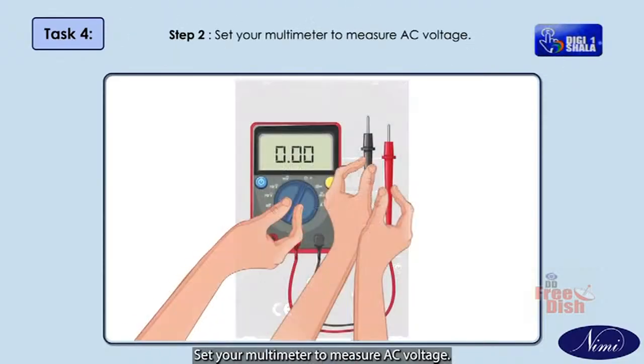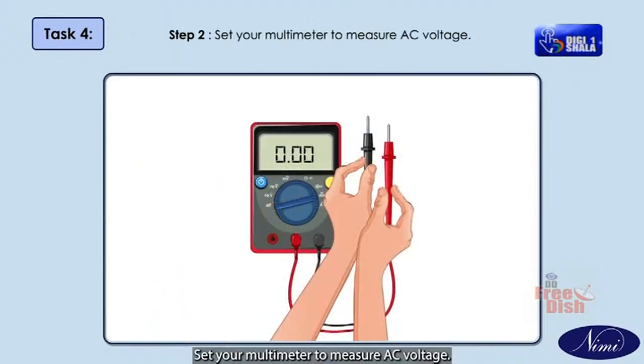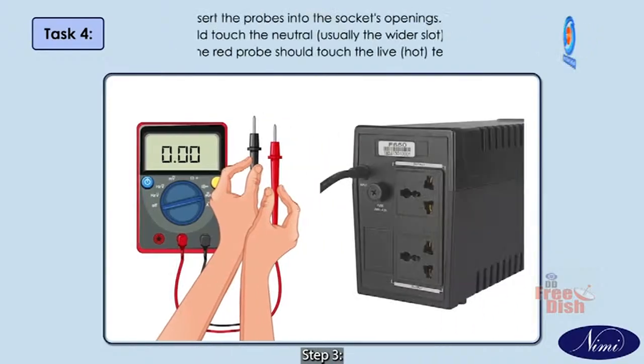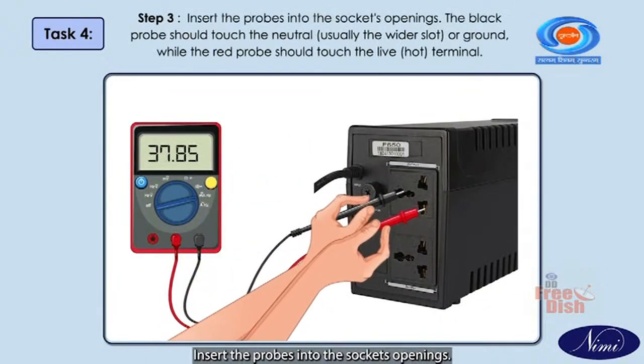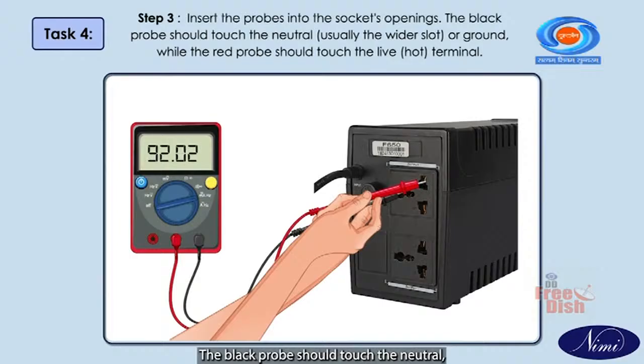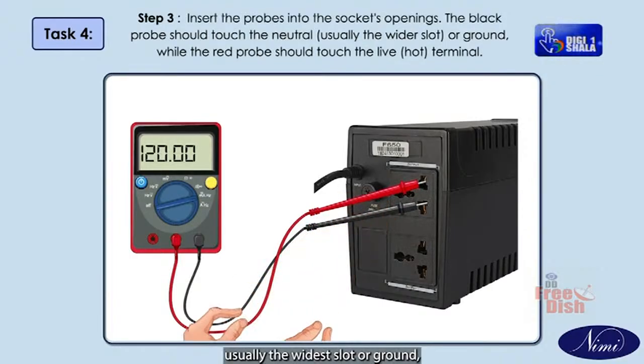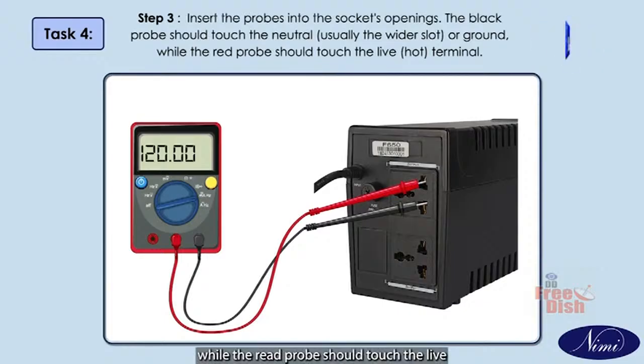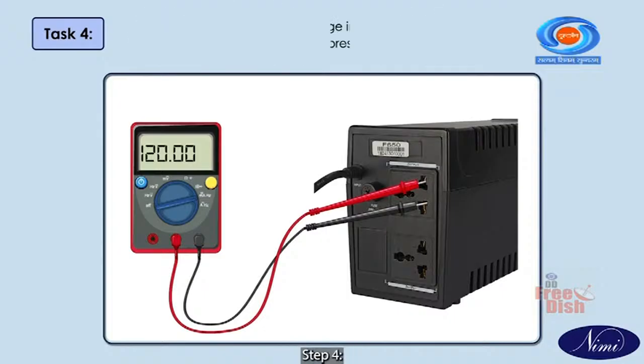Step 2. Set your multimeter to measure AC voltage. Step 3. Insert the probes into the socket's openings. The black probe should touch the neutral, usually the wider slot or ground, while the red probe should touch the live, hot terminal.